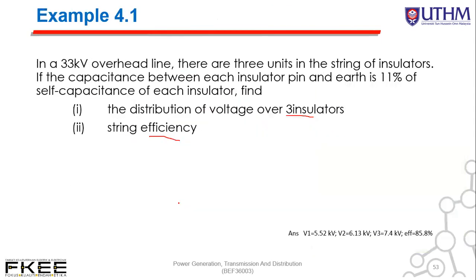Example 4.1: In a 33 kV overhead line, there are 3 units in a string of insulators. If the capacitance between each insulator pin and earth is 11% of the self-capacitance of each insulator, find the distribution of voltage over the 3 insulators and also the string efficiency. We have 33 kV, 3 units (since each disc is 11 kV × 3 = 33 kV), and 11% shunt capacitance. We want to find V1, V2, V3 and the string efficiency.